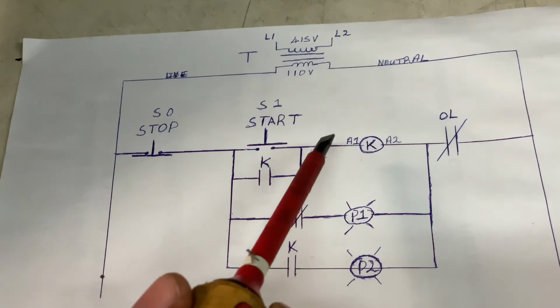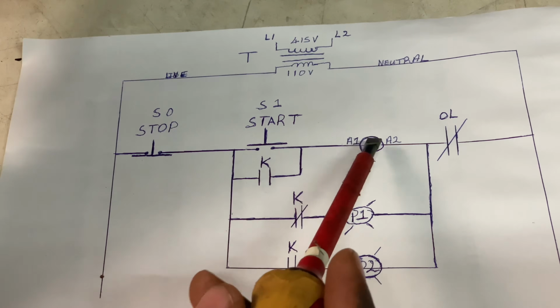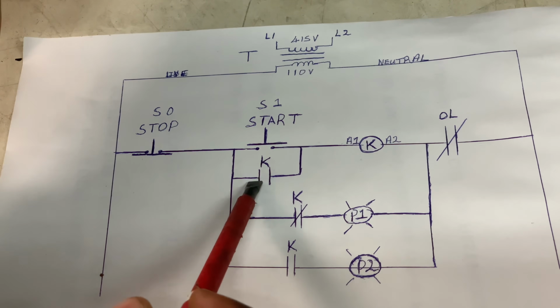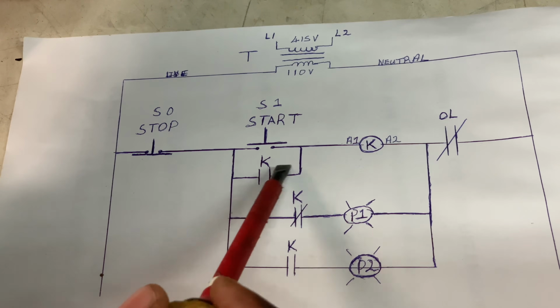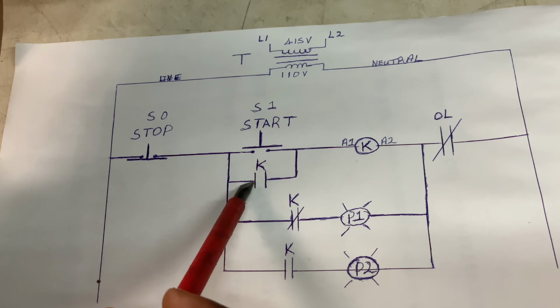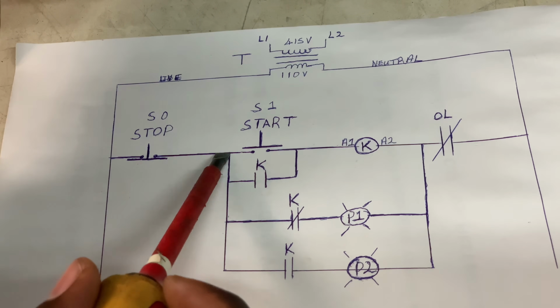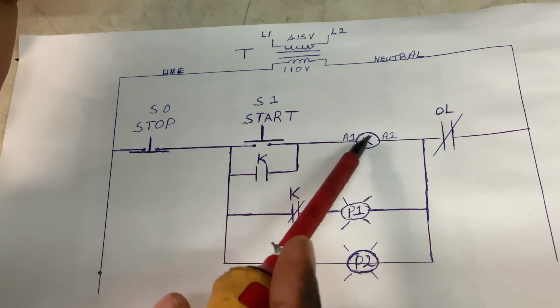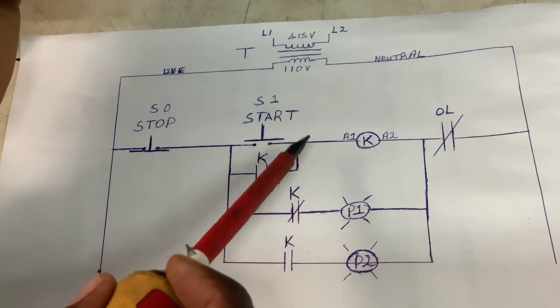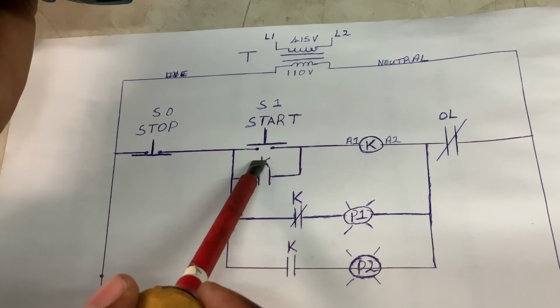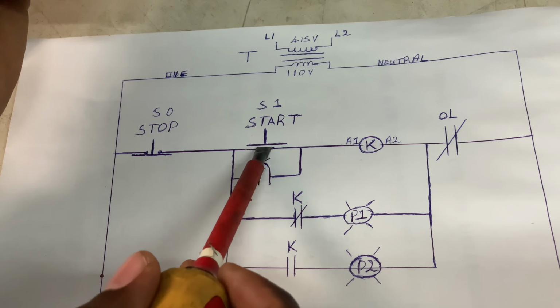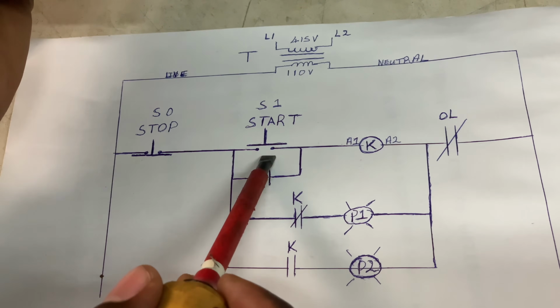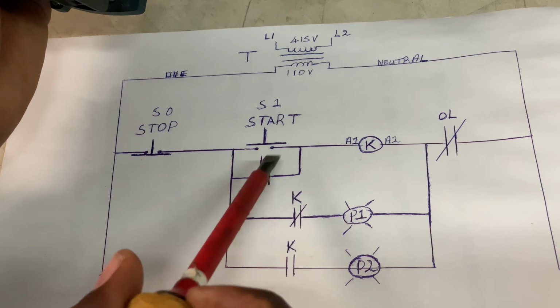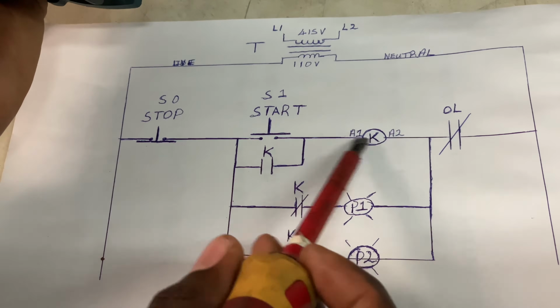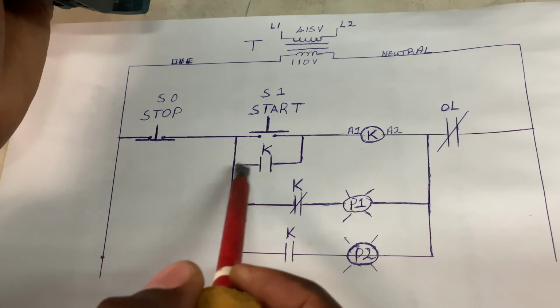Alright, so these are all contacts on the contactor. Alright, so when I press start, current flows through, energizes the coil. The open will close. Alright, so boom, this will close, and this will now be the flow for current here through here, and keep the contactor energized, because once you release your start button, it will open again, right? Spring return. So you just press it, energize. Once you release it, boom, you let it go, it opens again. So this will be the path for current flow to keep your contactor energized. This is also called the holding contact.